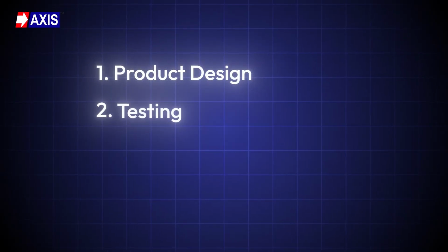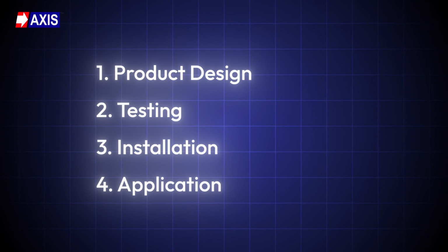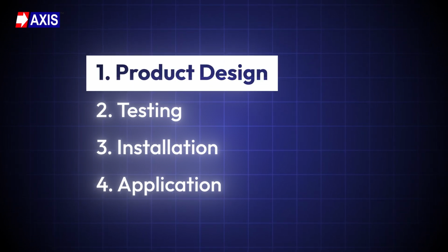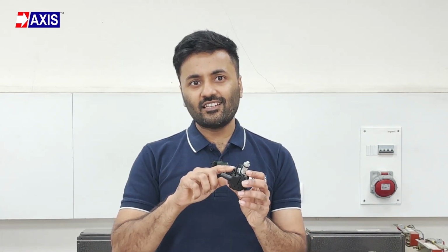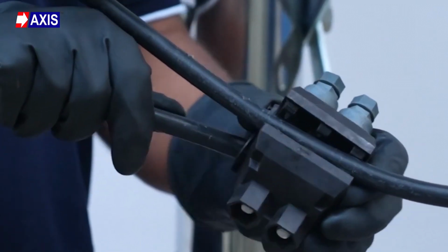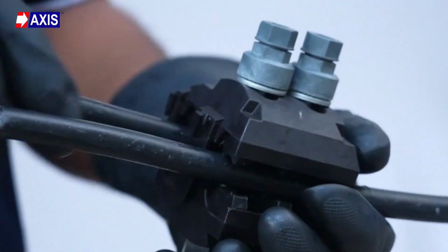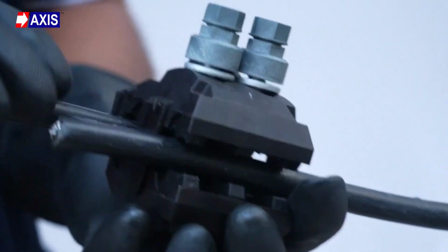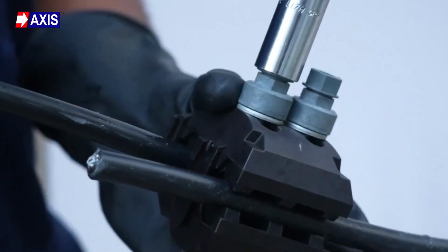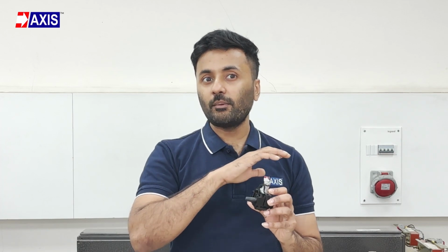This brings us to the main question. You're piercing a live cable, so how is it safe? The answer lies in four things: the product design, testing, installation, and application. Let's understand it from the design point of view first. The connector body is made of insulating material, so there is no direct access to any live part. The metal teeth that pierce the insulation are enclosed inside the connector, and it only makes contact with the conductor when the bolt is tightened. The tightened bolt is designed such that no live conductor parts are exposed, which means you do not come in contact with any type of live conductor during installation.